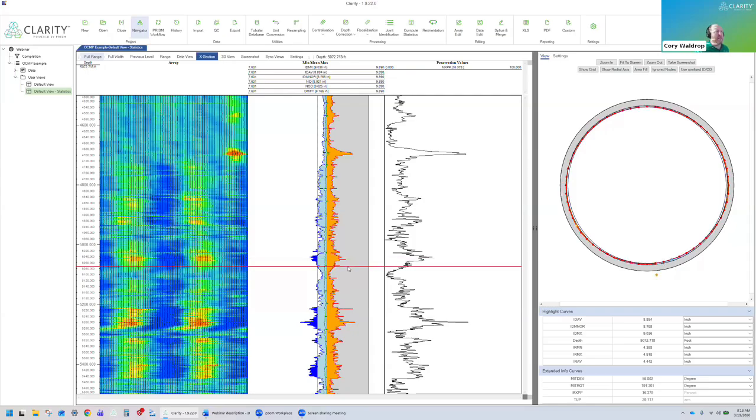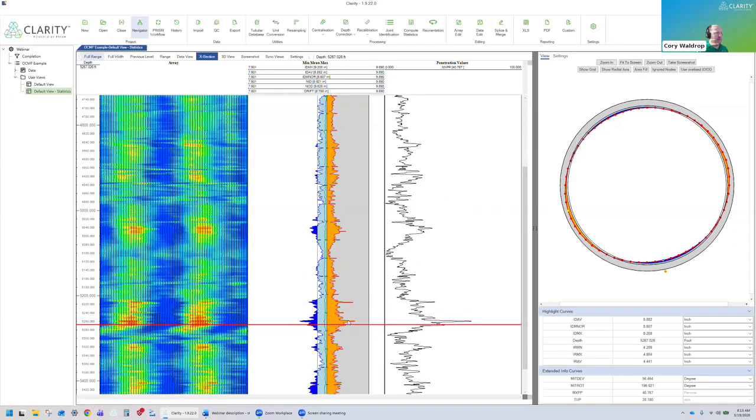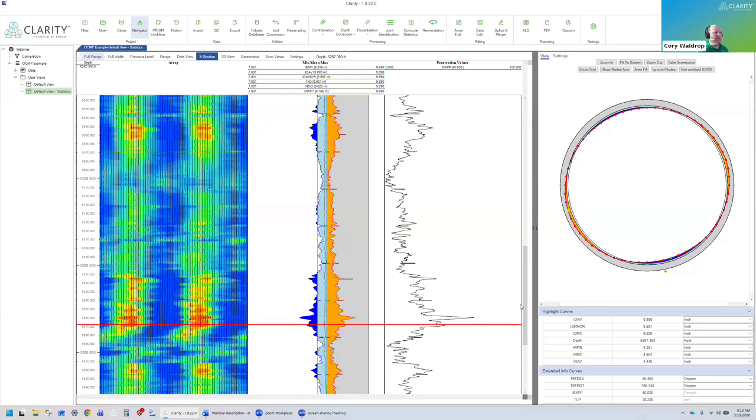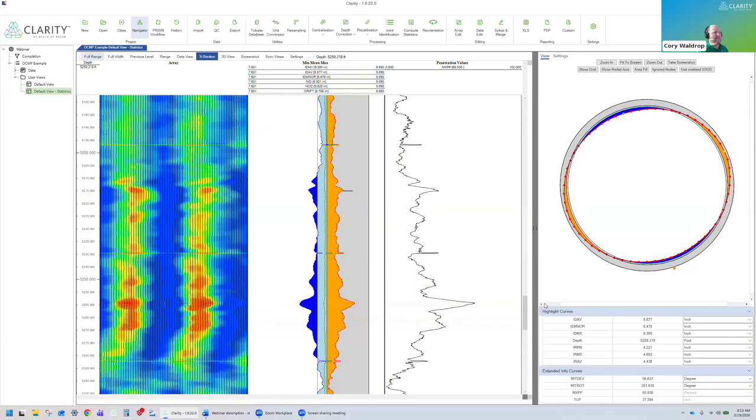To further demonstrate that, I'll zoom in. Looks like we have a kind of nasty oval feature here, and I'll highlight this in the cross section. So you can see in the cross section, we have a clearly ovalized cross section here, and anywhere you see this kind of orange color, that's going to demonstrate metal loss when we're reporting maximum penetrations because we're using a perfectly circular reference ID and OD to calculate your maximum penetration from.